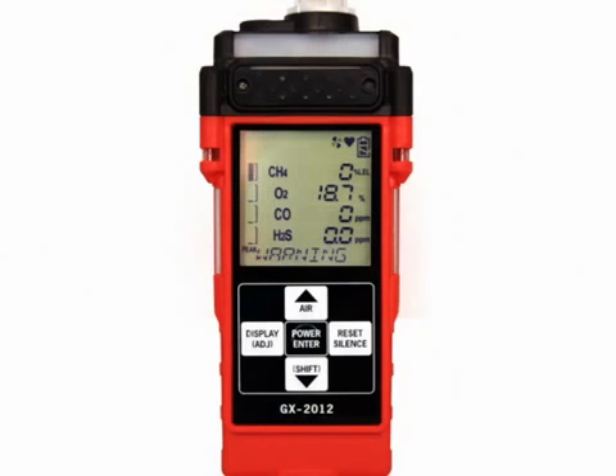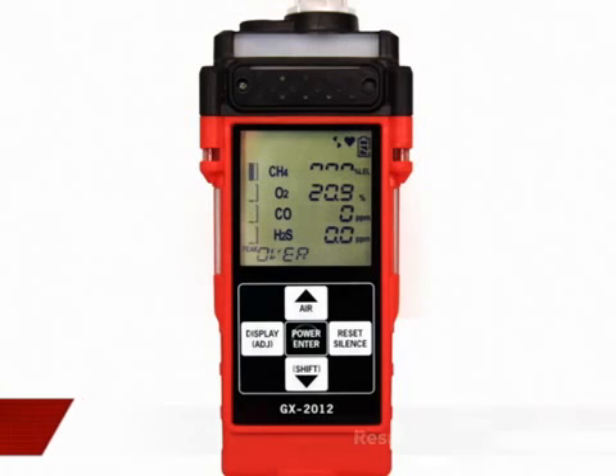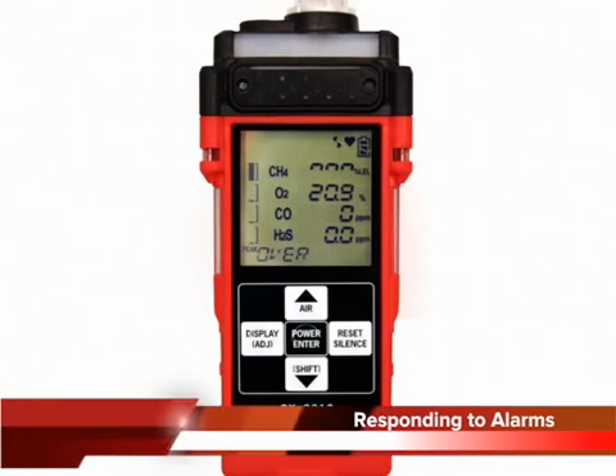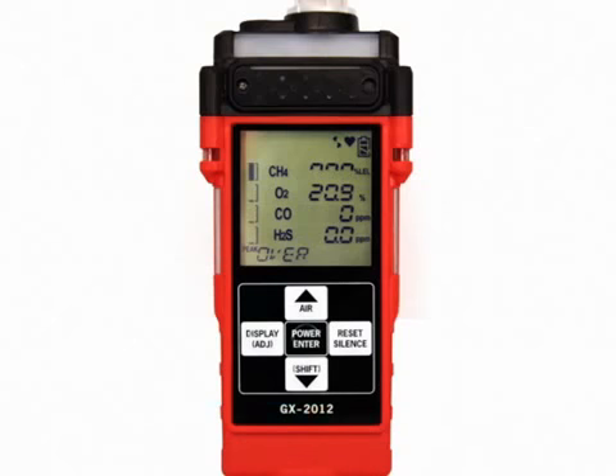With alarm silence set to off in maintenance mode, you cannot silence the buzzer while the gas reading is beyond the low alarm setting. An overrange condition may indicate an extreme combustible gas, toxic gas, or oxygen content condition. Take immediate action and confirm the gas levels in the area with a different GX2012 or with another gas detecting device. Determine which gas alarm has been activated.